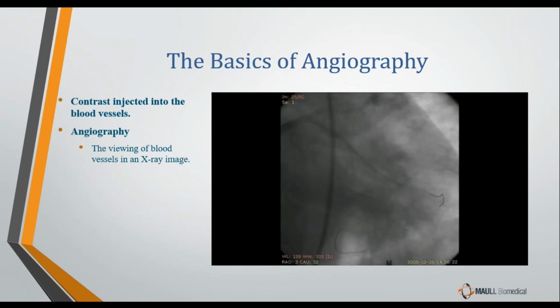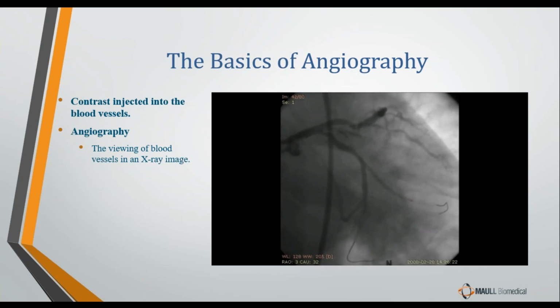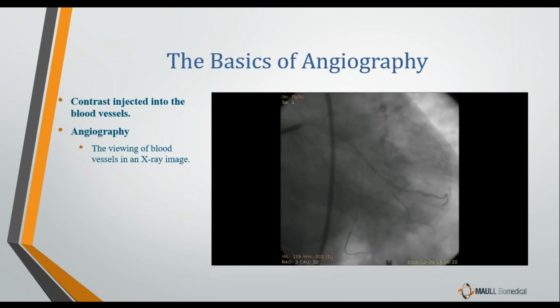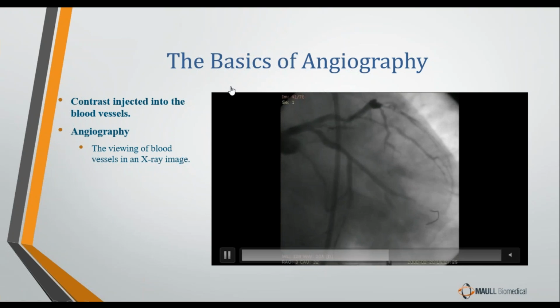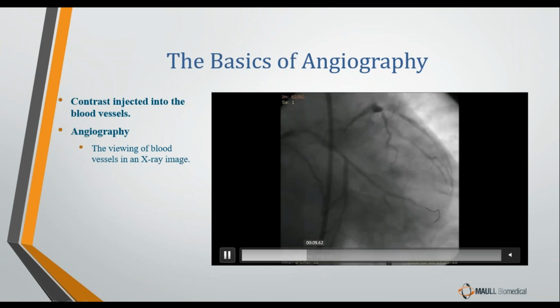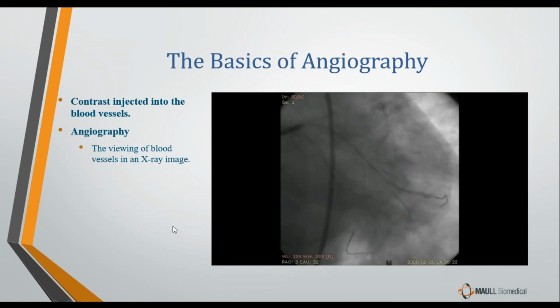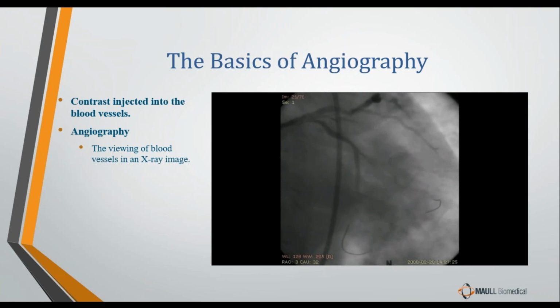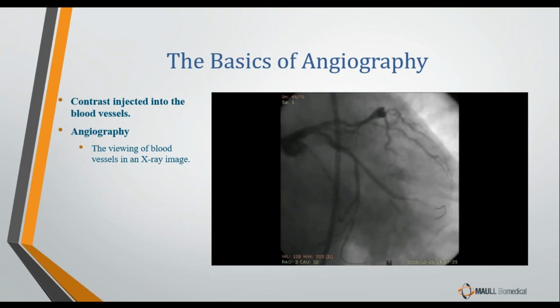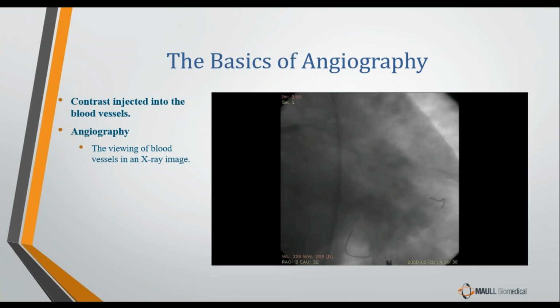That is what the contrast injector is for. You'll see here, this is a fluoroscopic image without contrast. For those of you who are not imaging personnel, fluoro is basically an X-ray image viewed in real time on a monitor. Now, this is a very good example of how effective contrast fluid is. You'll see here on your fluorograph, right now, we don't really see the blood vessels too well. They don't show up on the image very well because they're being penetrated by X-rays. As we inject contrast fluid into the blood vessels during the procedure, you can see that the blood vessels darken up and show up on the image.